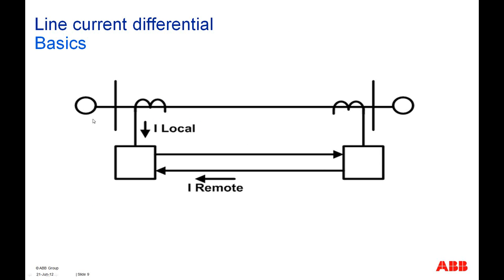As we talked about, this is the local station. In a line differential protection scheme we have to define what the local station is and what the remote station is. This is the box which measures the local current, and it gets the information from the remote end relay, and then it processes the information in this box. There are different topologies and different ways of communication, and we will talk about those. But the basic idea is that the box takes the information locally, and then takes the information remotely from the remote end, and then processes the information and compares it with the threshold values to arrive at a decision of tripping or not.